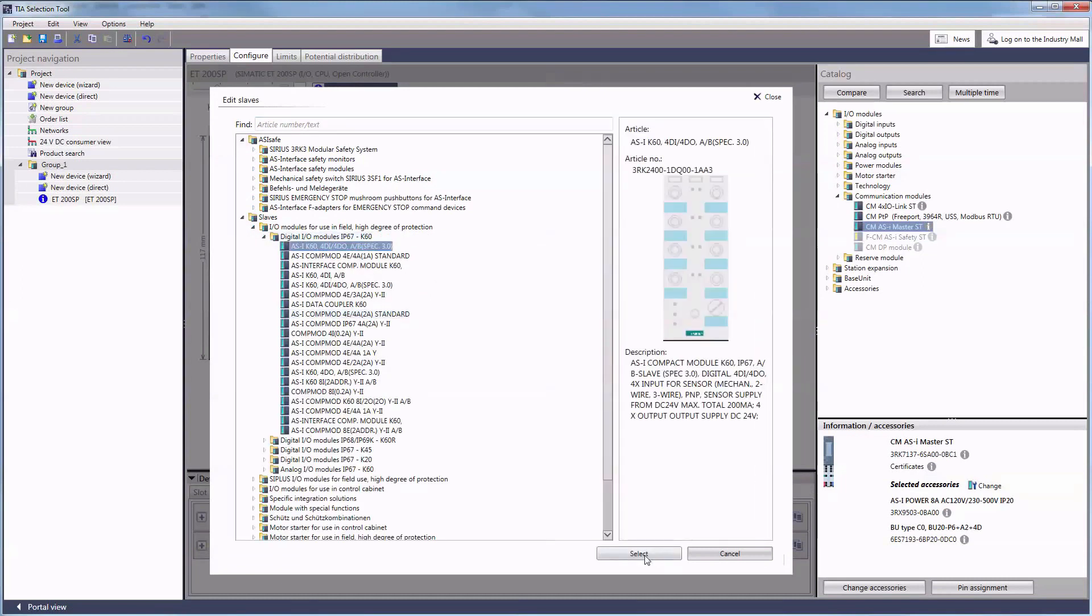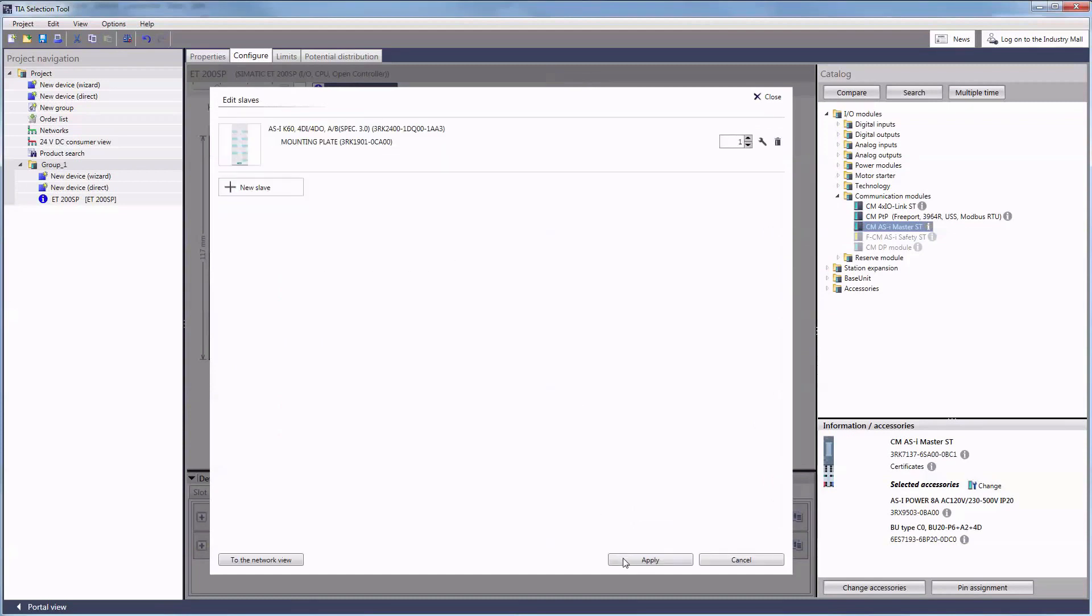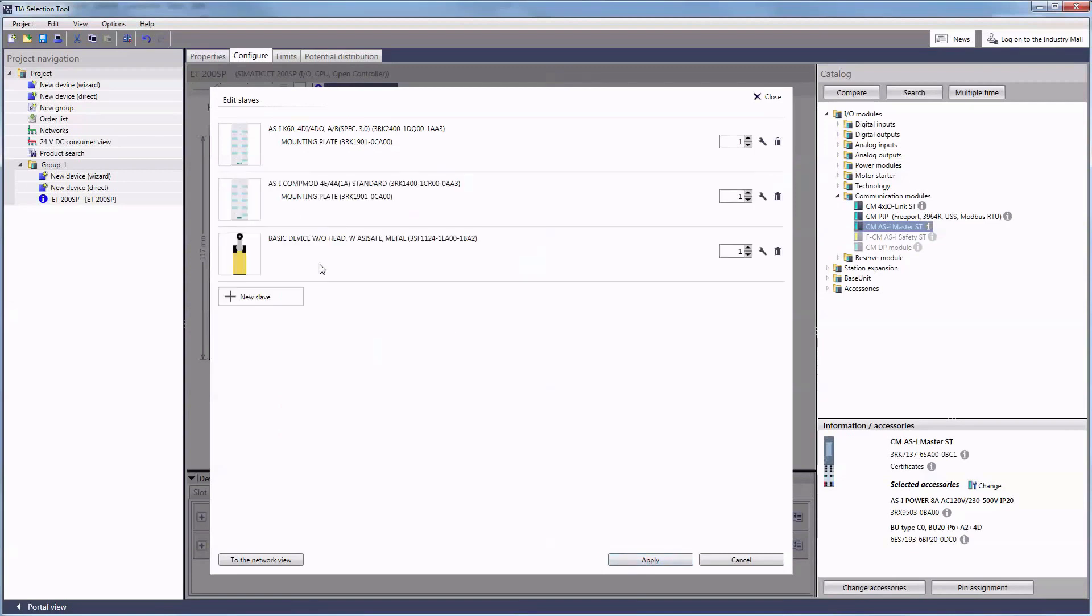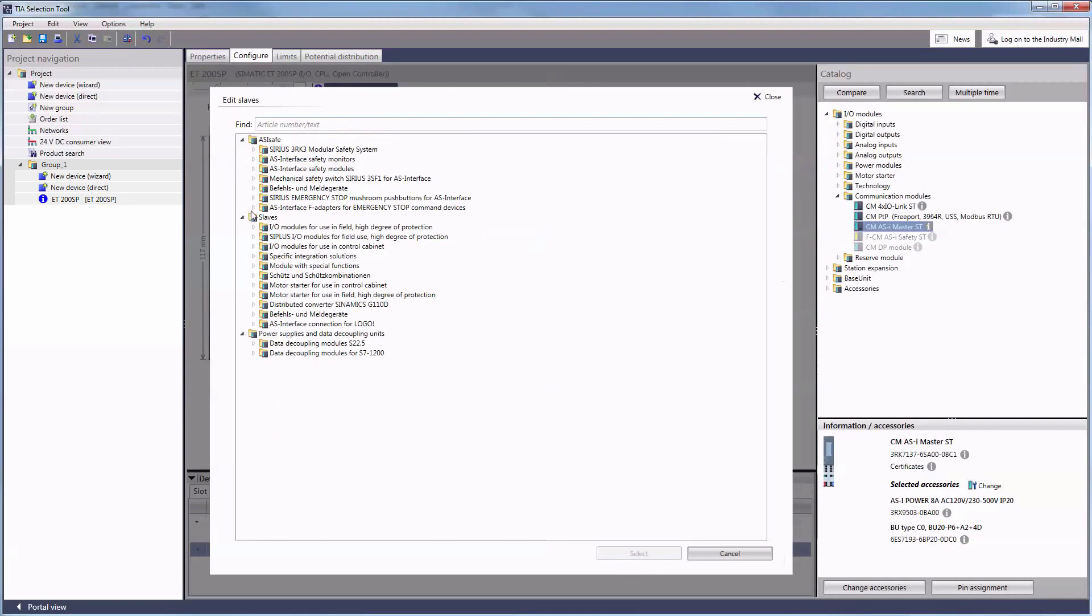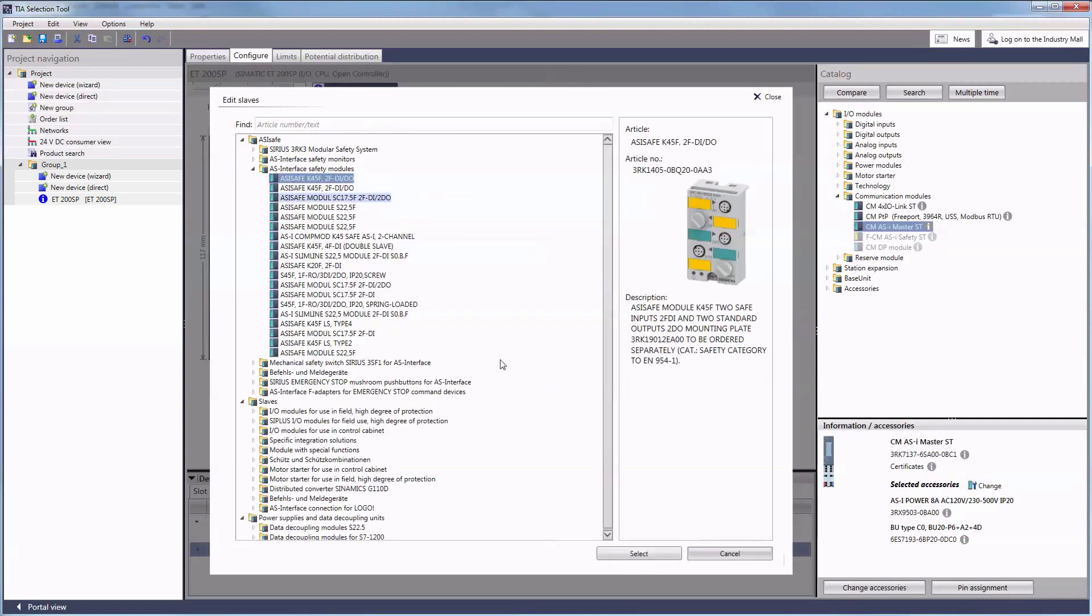Up to 62 slaves can be connected to the ASI master and are supplied with power over the ASI interface. The AS interface also enables the direct integration of safety components.